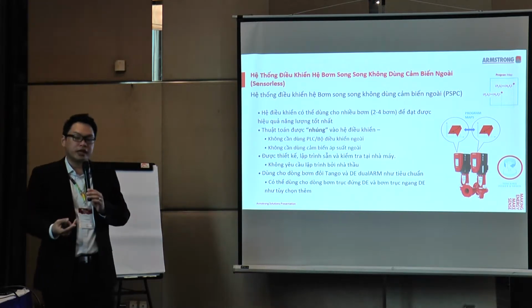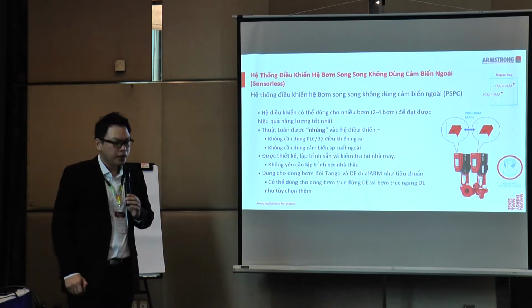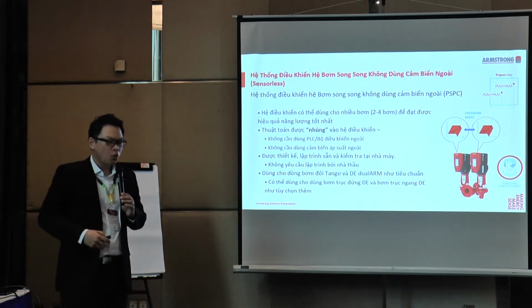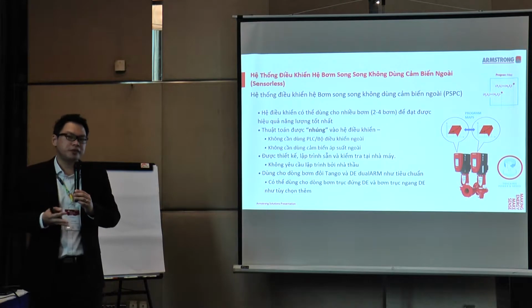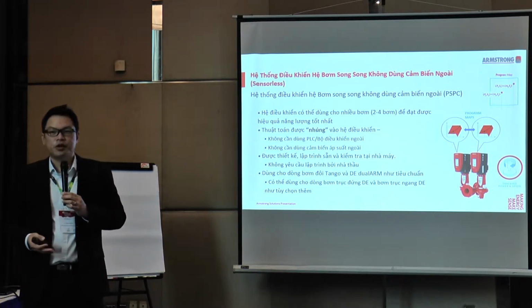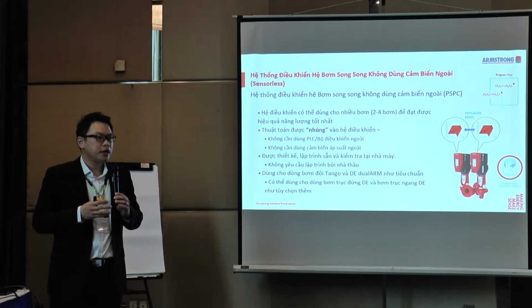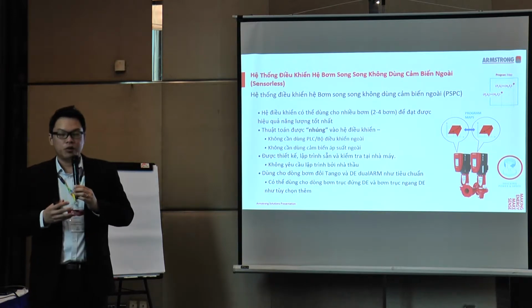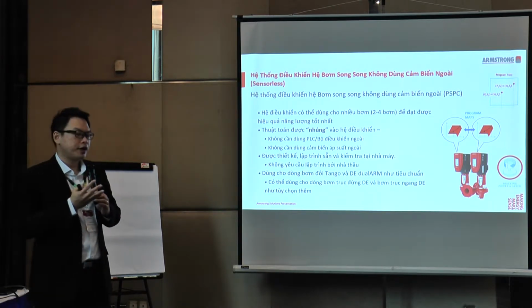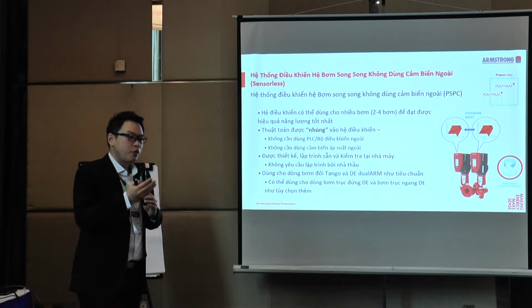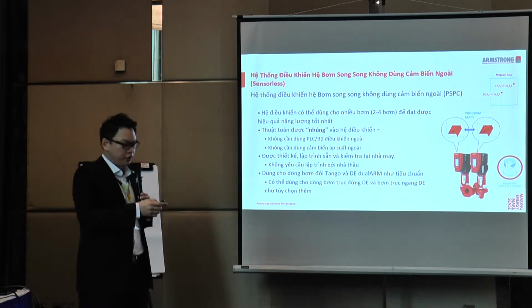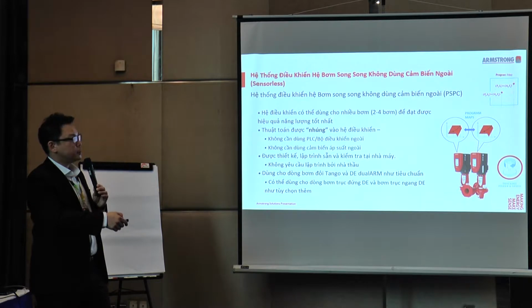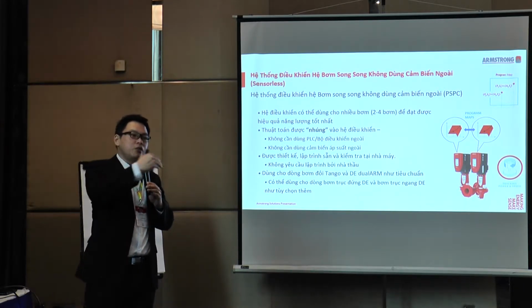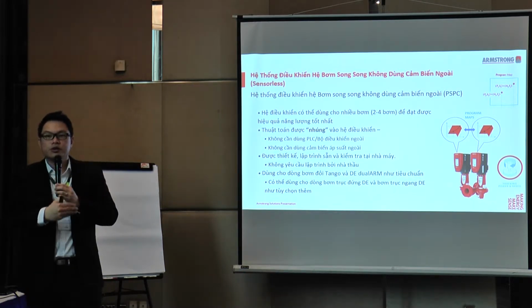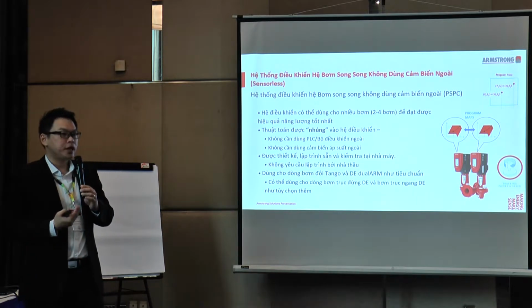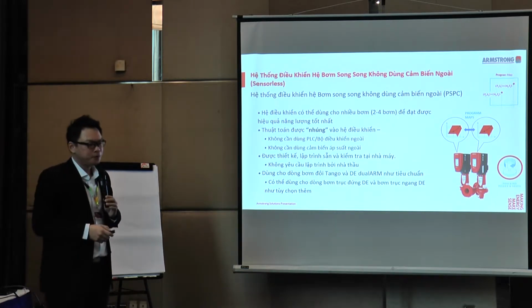So with our Tango pumps or even our design envelope pumps, we do not need a DP sensor. Okay? The question you might want to ask me is, without a DP sensor, how do you know where the pump is operating? It is because all the data has been preloaded, pre-programmed, and pre-tested at factory. The data we collect at factory is 4 points at each speed: power and speed, flow and head. These are the 4 parameters that we collect during our test at factory, and we embed them into the controls. So it is able to detect the actual requirement of the system, and it's able to control it sensorless.